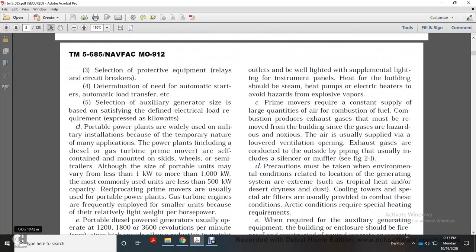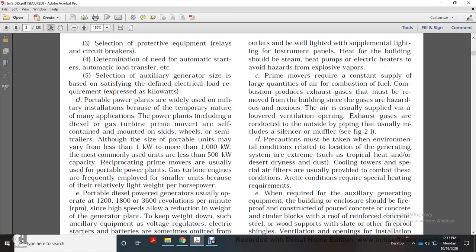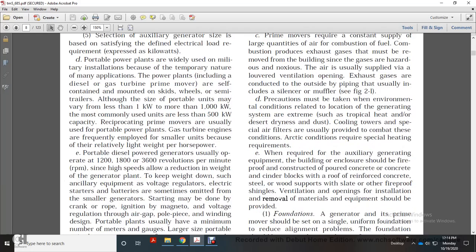Portable power plants are widely used in military installations, covering the temporary nature of many applications. They include diesel, gas turbine, and other prime movers, self-contained and mounted on skids, wheels, and semi-trailers. The size of portable units may vary from less than 1 kilowatt to more than 1,000 kilowatts. The most commonly used units are less than 500 kilowatt capacity. Gas turbine engines are frequently employed for small units due to their relatively light weight per horsepower.